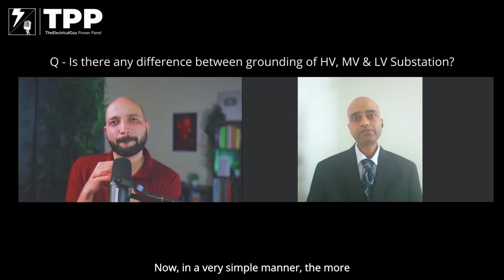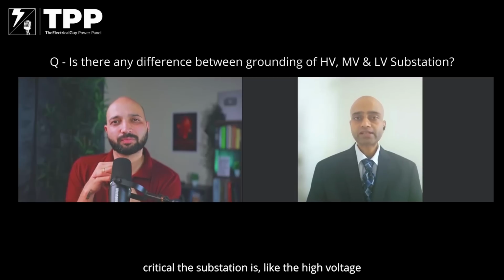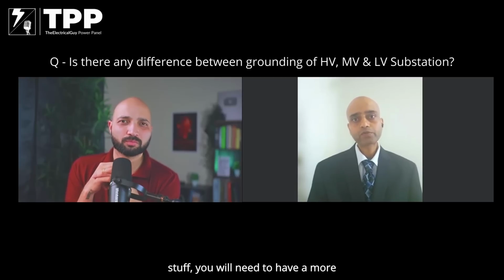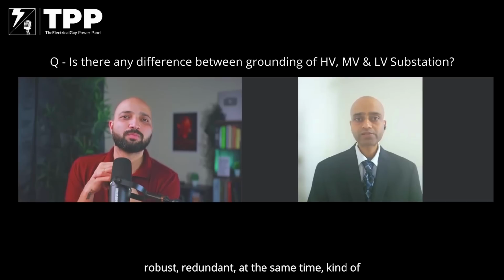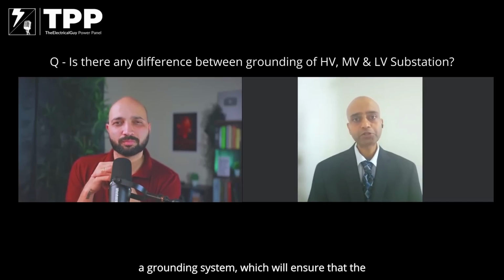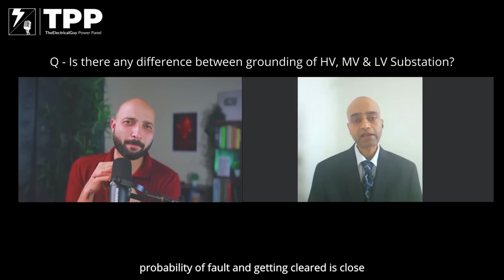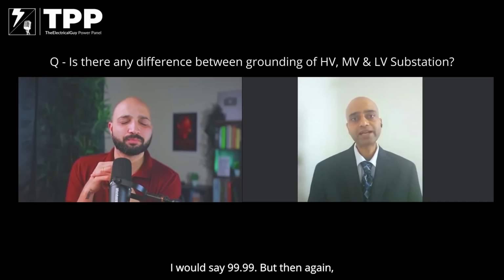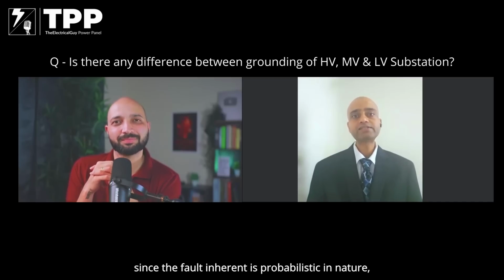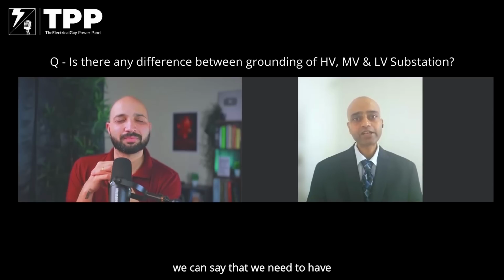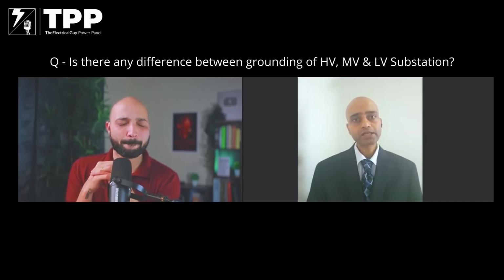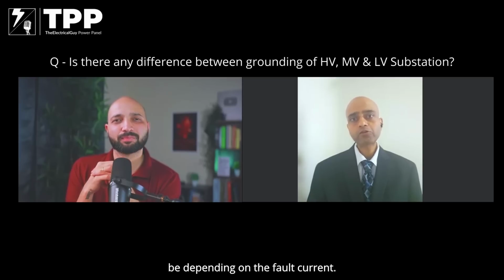Now, in a very simple manner, the more critical the substation is, like the high voltage stuff, you will need to have a more robust, redundant grounding system which will ensure that the probability of a fault being cleared is close to 100%. I would say 99.99. But then again, since the fault is probabilistic in nature, we can say that we need to have a more robust system for the high voltage. For medium voltage, it may or may not be, depending on the fault current.